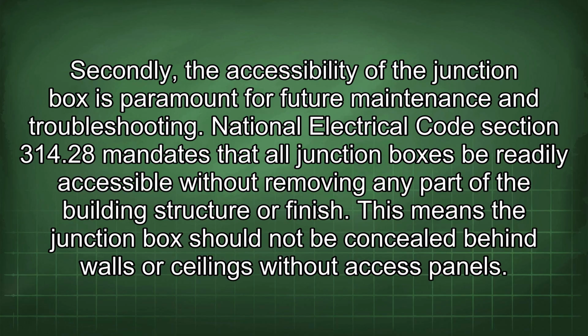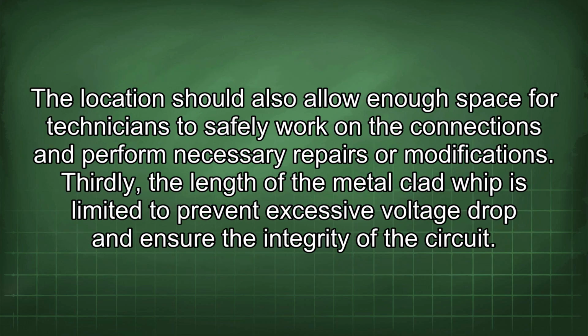Secondly, the accessibility of the junction box is paramount for future maintenance and troubleshooting. National Electrical Code Section 314.28 mandates that all junction boxes be readily accessible without removing any part of the building structure or finish. This means the junction box should not be concealed behind walls or ceilings without access panels.